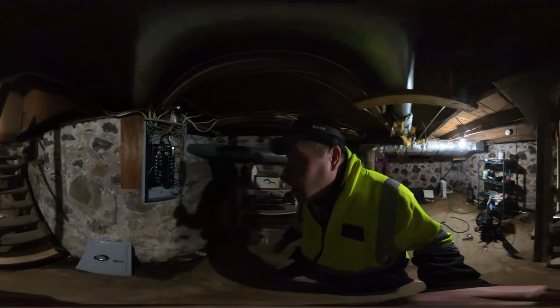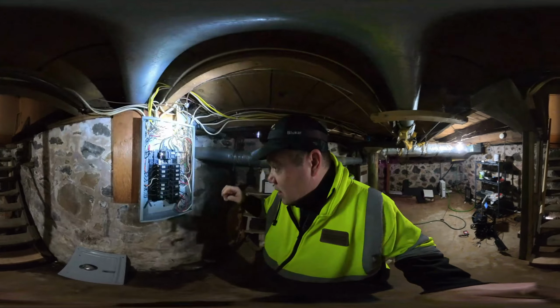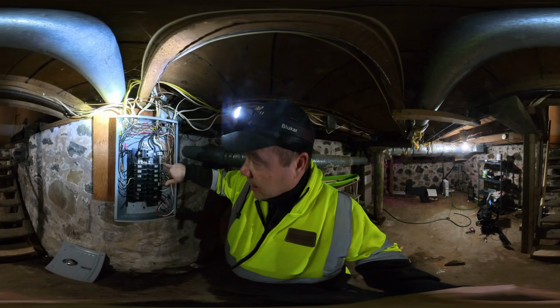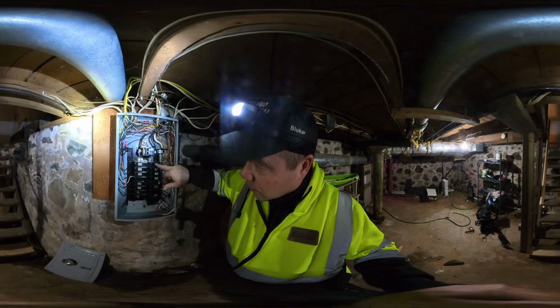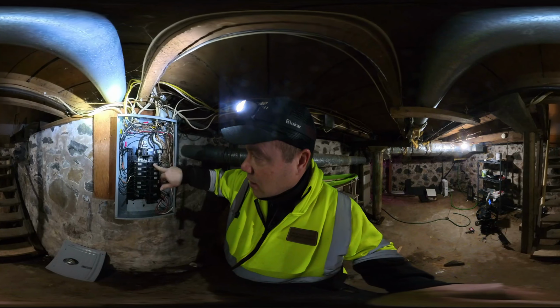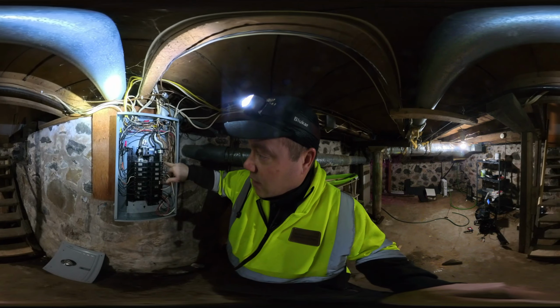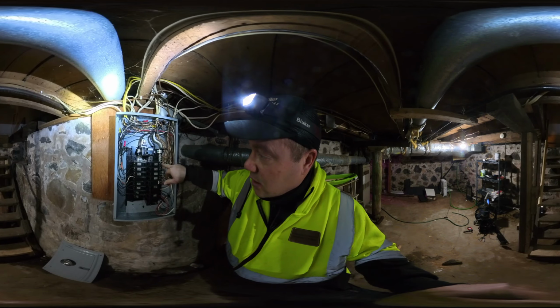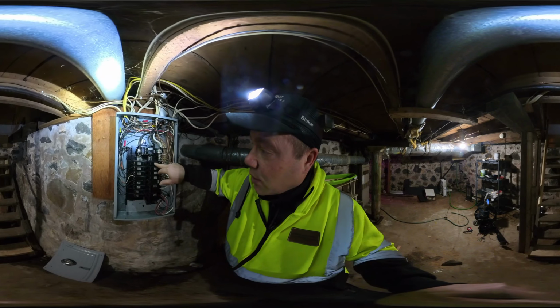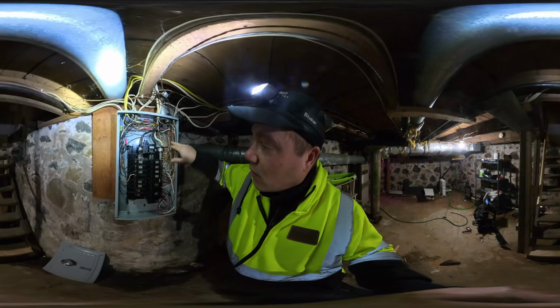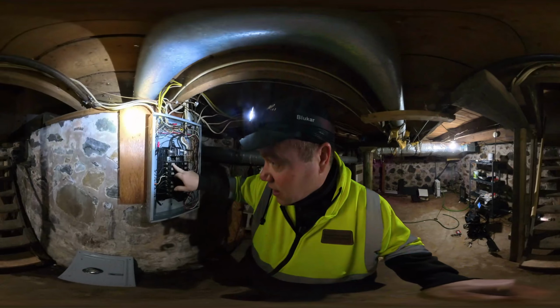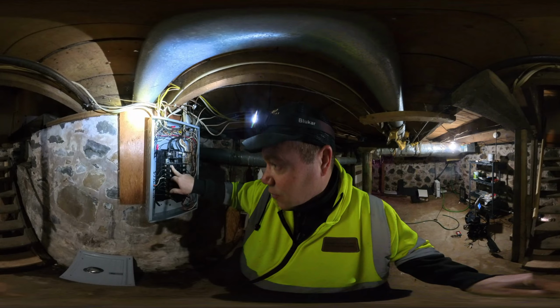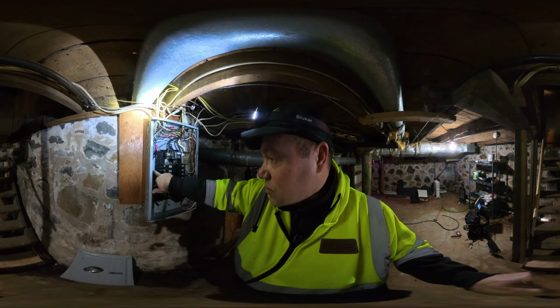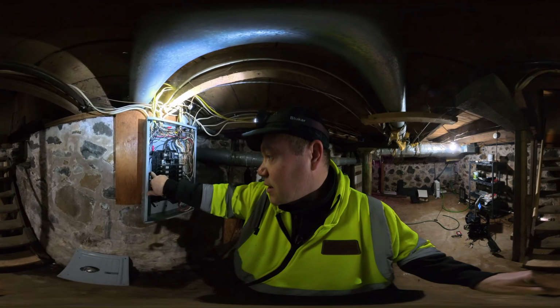Some of my areas of concern are the conductors going into the panel. Let me turn on my light. So we've got a 15 amp conductor here going into a 20 amp breaker. That's the problem on this part, because a smaller conductor going to a bigger breaker could potentially cause a wall fire. On the flip side, we have a 15 amp breaker going to a 20 amp conductor.